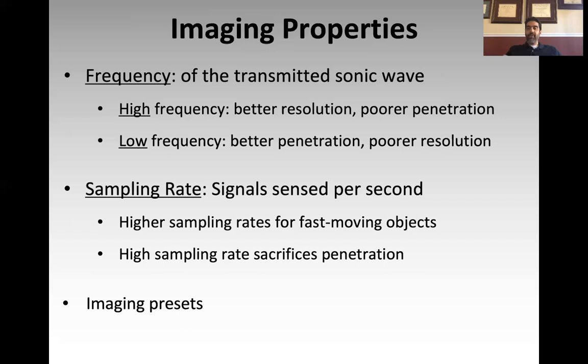The opposite is true with the cardiac setting. If you turn on the cardiac setting, it shifts the frequency higher and increases the sampling rate, giving you the ability to look at the heart — a relatively superficial, fast-moving structure — with high resolution. But if you try to look at the abdominal aorta using the cardiac setting, it won't look so good. That's how frequency and sampling rate modify your ability to optimize imaging of various structures.